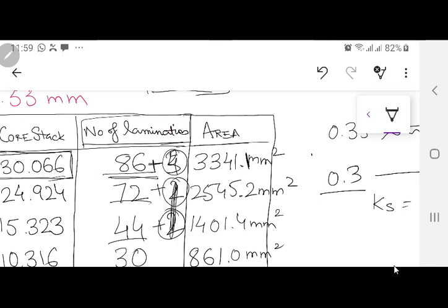Okay? So whenever there is a cutting process, either it has to be laser cutted, which is certainly again expensive, or whenever you are doing the cutting, it has to be burr free. Burr free है उसके sides के ऊपर आपके पास burr ना हो, and it is not bended also. Otherwise, when you are going to stack up the laminations, you are going to have a lot of air gaps over there. And air gap, you all know, is detrimental for your magnetic field over there.